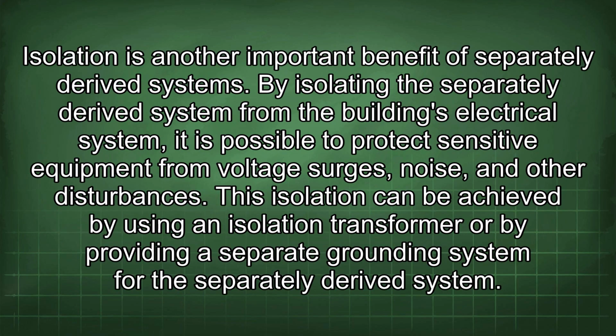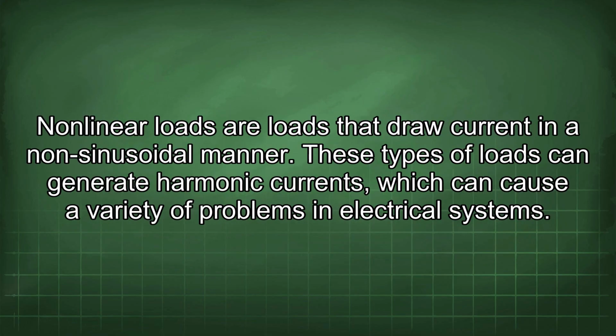Isolation is another important benefit of separately derived systems. By isolating the separately derived system from the building's electrical system, it is possible to protect sensitive equipment from voltage surges, noise, and other disturbances. This isolation can be achieved by using an isolation transformer or by providing a separate grounding system for the separately derived system.